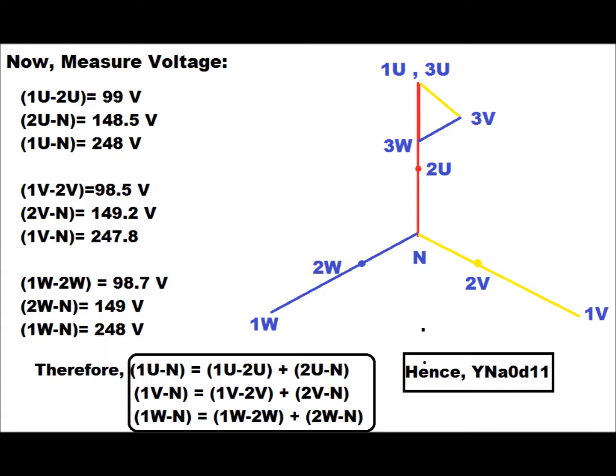For the yellow phase, the voltage between 1V and 2V comes to 98.5 V, between 2V and N comes to 149.2 V, and between 1V and N comes to 247.8 V. For the blue phase, the voltage between 1W and 2W comes to 98.7 V, between 2W and N comes to 149.4 V, and between 1W and N comes to 248 V.